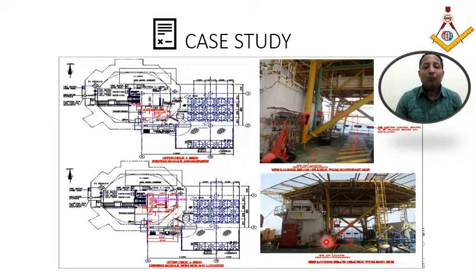For this particular room to be air conditioned, considering the space requirement over here, an air cooled package unit is proposed to supply the air, because it should create a pressurization also inside, and a package unit can create pressurization very effectively. By means of supply air being supplied and the required amount of pressure with the ducting arrangement and balancing, it can be achieved. Now let's see how it can be done, which I have covered in the subsequent slide, and you will see how it's been done and how it looks.